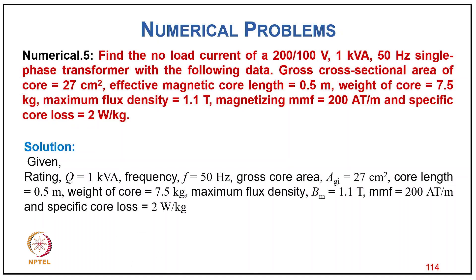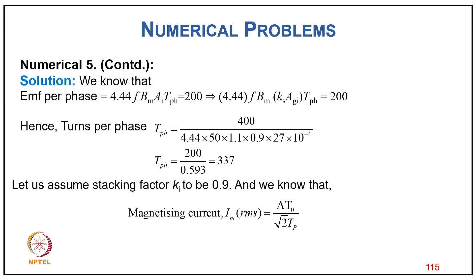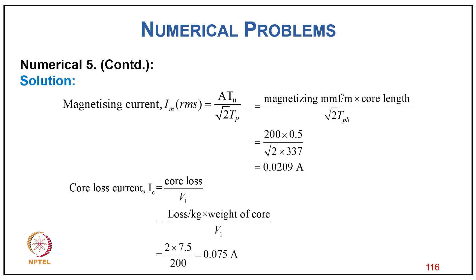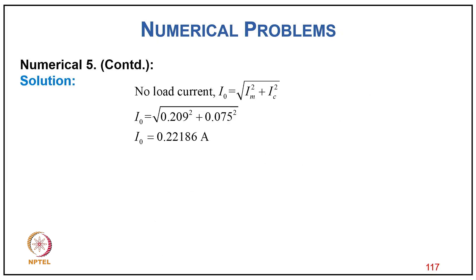Numerical problem 5: Find no-load current of a 200/100 V, 1 kVA single-phase transformer with: gross cross-section 27 cm², effective magnetic length 0.5 m, weight of core = 7.5 kg, maximum flux density 1.1 T, magnetizing MMF 200 AT/m, specific core loss 2 W/kg. From E = 4.44×f×Bm×Ai×Tp: primary turns Tp = 337 (with stacking factor Ai×0.9). Magnetizing current Im = AT₀/(√2×Tp) = 0.0209 A. Core loss component Ic = (2×7.5)/200 = 0.075 A. No-load current I₀ = √(Im²+Ic²) = 0.22186 A.